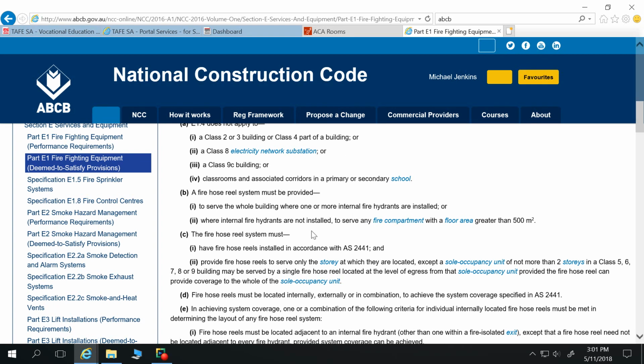So knowing 36 metres, you've got to think about where you can install those fire hose reels. They're not going to stick out and obstruct the path of travel for somebody going to an exit. Another thing we have to do is look at the location of those fire hose reels as well. So every hydrant requires a fire hose reel. Covered that bit. What have we got here? Might just pause that. Yep, so back to it.